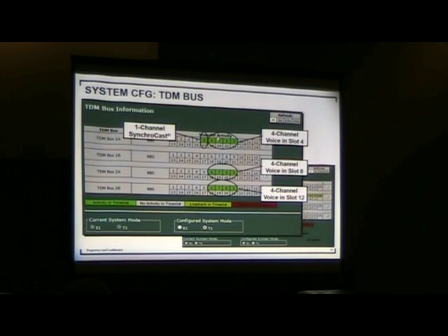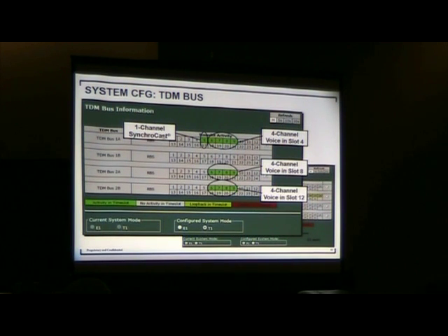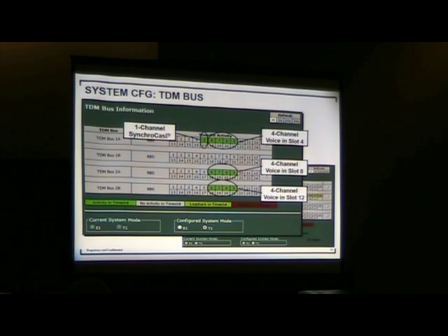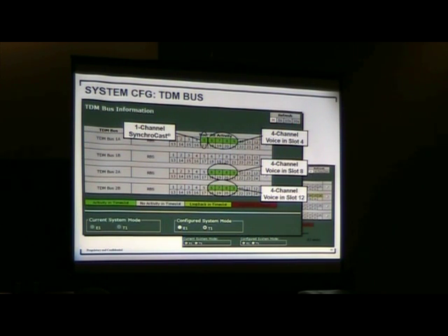It's important that the Synchrocast data from the GPS also be paired with the voice channels you're trying to time-align in the field, by bundling them into one common stream. When they're played out at the other end of the system, the Synchrocast data is decoded and time-aligned on the play-out side of the field shell, so the audio will also be time-aligned with it. Any Synchrocast or simulcasting voice channels need to be in a common stream with the Synchrocast module.